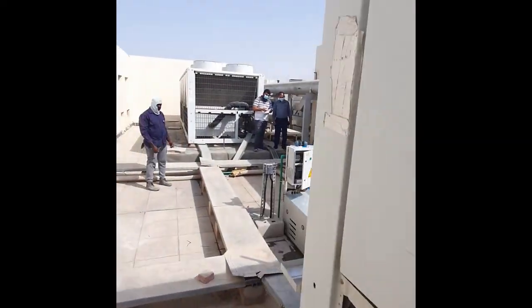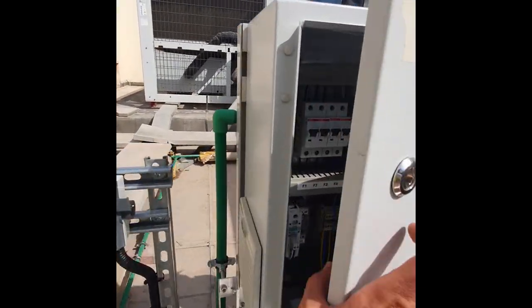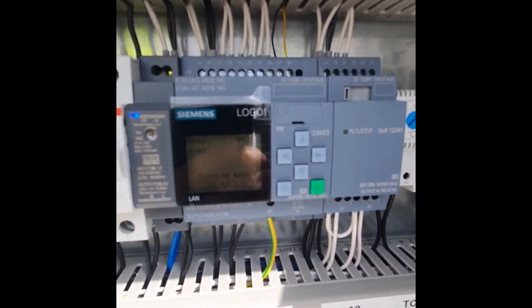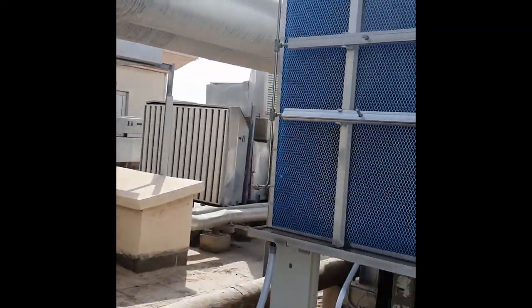And now let's have a look at the ambient weather conditions. As we can see here, the ambient temperature is plus 44 degrees Celsius with 28% relative humidity. That means the delta T achieved by smart cooling is fluctuating between 19 and 21 degrees Celsius.